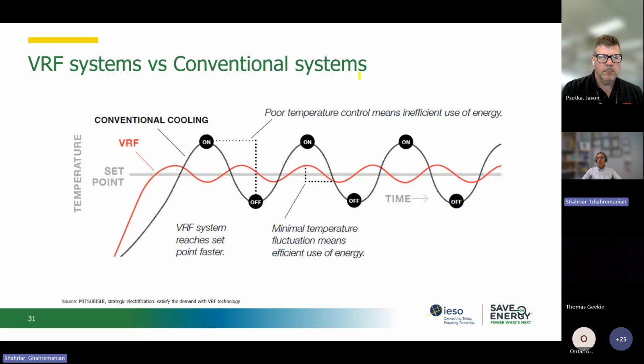If we compare the VRF system with a conventional air conditioning system, it's good to take a look at that in cooling mode. The black line shows how the air conditioning system that we have works. You see that it goes on and then off, basically it's short cycling with higher peaks. But a VRF system reaches a set point faster, because it is more efficient, and it doesn't short cycle on high peaks or low peaks that much. So this gives us minimal temperature fluctuation, which means more comfort for the building occupants. At the same time, it also means less energy use for the VRF system, which means that the VRF system has a higher efficiency compared to the conventional air conditioning system that we have. So this is another comparison of the VRF with the conventional cooling system.